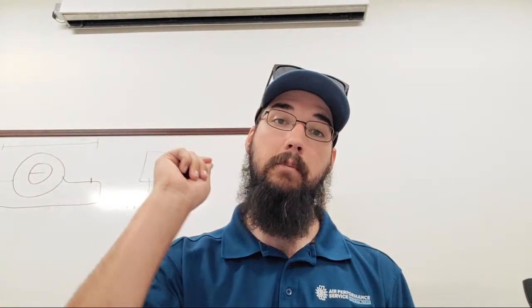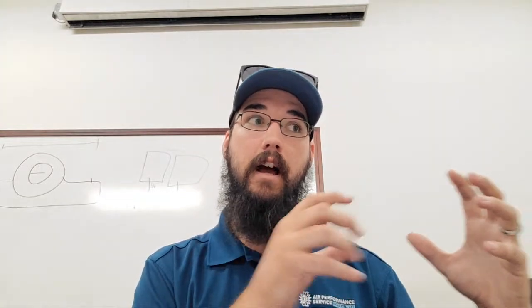So how we overcame that was by giving an alternative flow source: running a 1/4-inch hose from the discharge to the suction side directly, completely bypassing all the coils. After we drained the flash tank, we didn't have the full column of liquid in it anymore, so it was truly vapor at this point. Then by activating the economizer valve, we were able to overcome that vapor lock, because we caused the whole system to kind of shift, if you will. I can't explain it in a really in-depth or technical way, but it created a shift in that oil placement. And when that shift happened, it allowed us to start pulling that oil through, and it broke the lock.